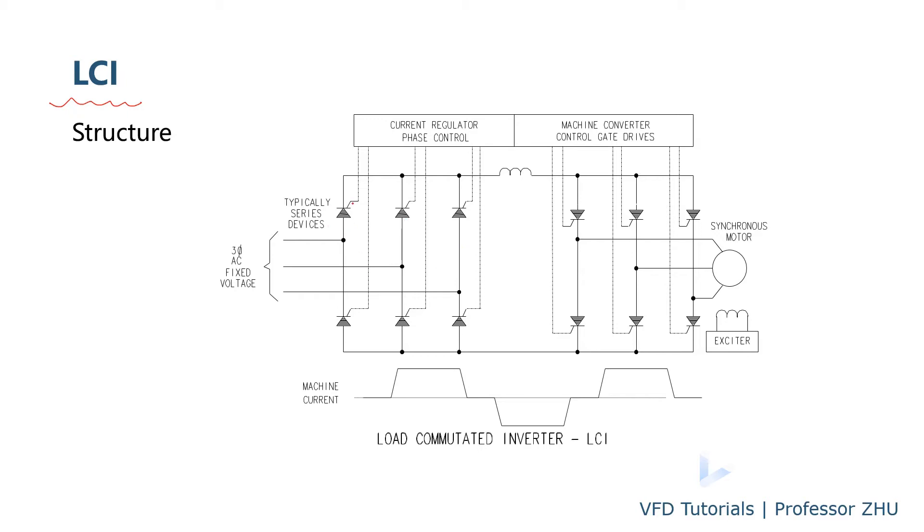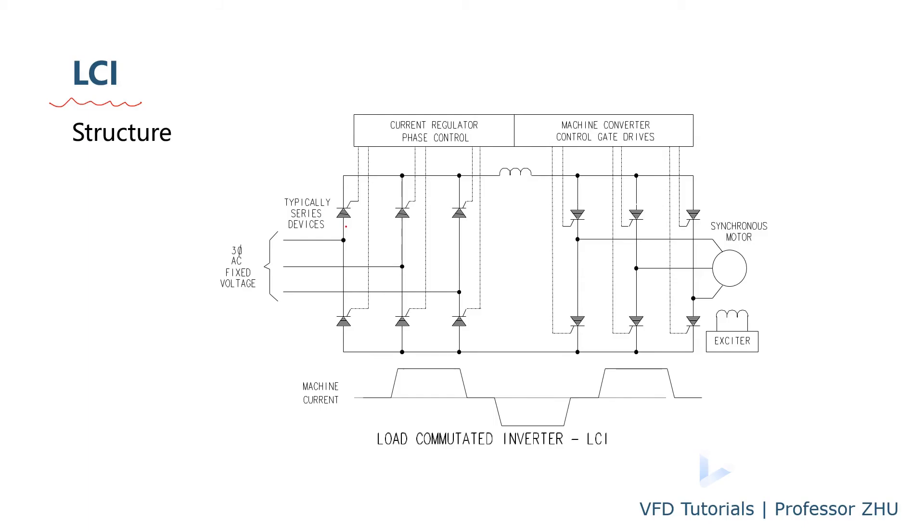This is why we call the load commutated inverter. They use the load, the synchronous motor, to do the commutation. You cannot use induction motor for this kind of drive topology because you need the current leading the voltage on the motor side. On the rectifier side, also use the SCR. So the power factor will be very low at the low power output.